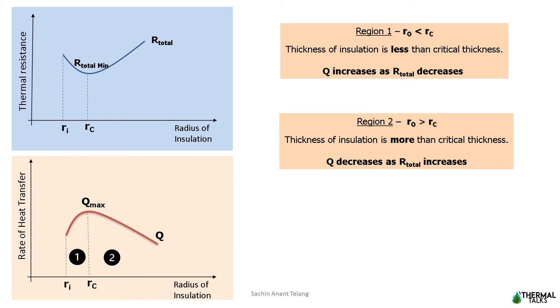Let us come to Region 2, where thickness of insulation is more than critical thickness — that is, if the value of Ro is greater than Rc. The further addition of insulation decreases the heat flow by increasing the total thermal resistance. Such a case is applicable in insulating steam pipes and refrigeration pipes, where the idea is to restrict the heat flowing out of the system.